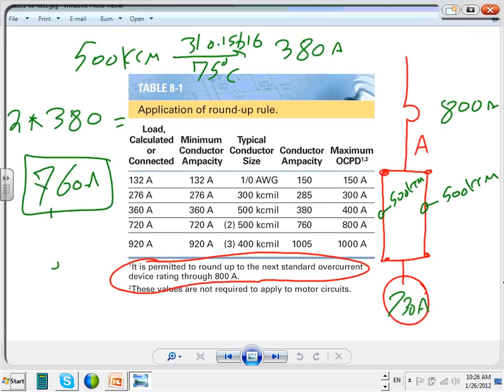If you take this one to 240.6, what's the next standard? 800. These are the exceptions in the code. It says if the conductor's ampacity does not correspond to a standard rating, 760 is not a standard, so I need to put in a circuit breaker. I can put 700, or I can go to 800. They allow you to go to 800, only up to 800. Now, if I have 1,000, I have to match the 1,000 amps.